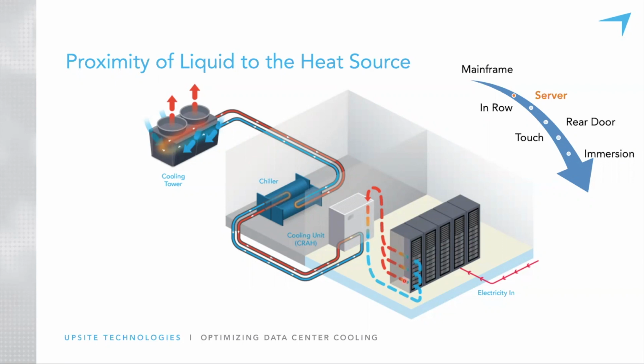This is when we have air cooling. We have air as the first loop. Air is what's picking up the heat from the source and carrying that heat to a perimeter cooling unit, be it a CRAH in this case with a chilled water loop, or it could be a CRAC air conditioner system with a refrigerant cycle. But we have the perimeter cooling units picking up the heat from the air, and now the heat enters a liquid, and the liquid is going to carry the heat away, either directly outdoors if you have a compressor-based system, or to the chiller again if you have a chilled water system, passing it to the condenser water and out to the cooling tower again.